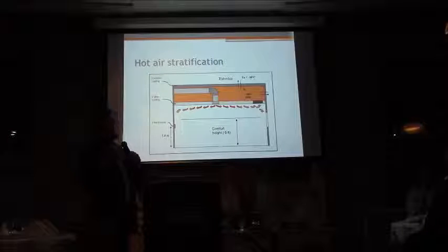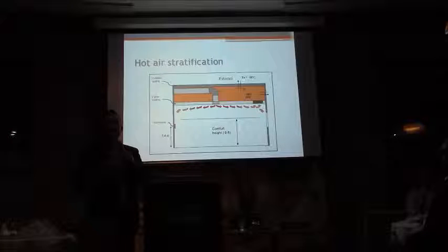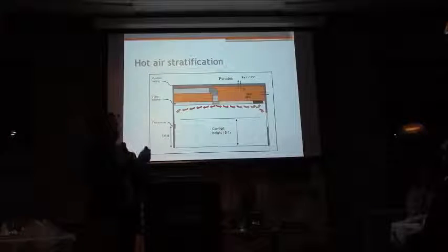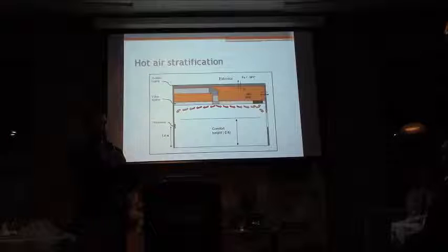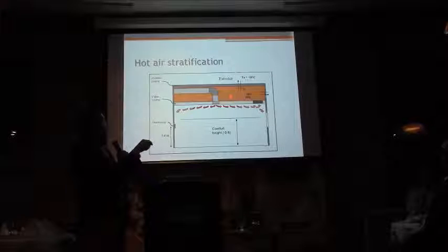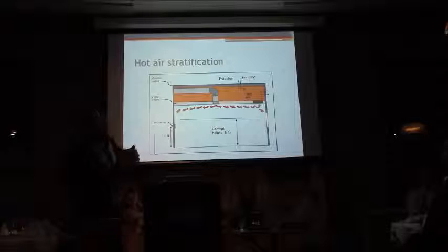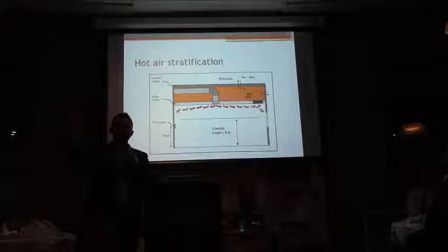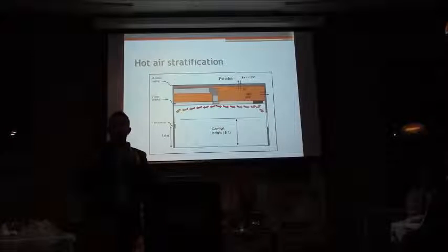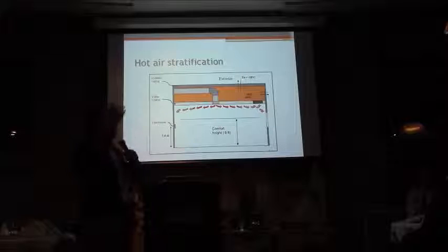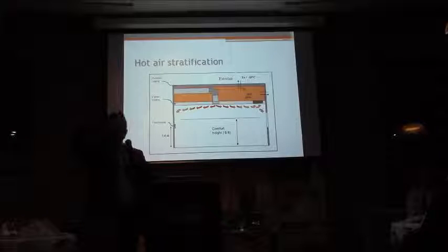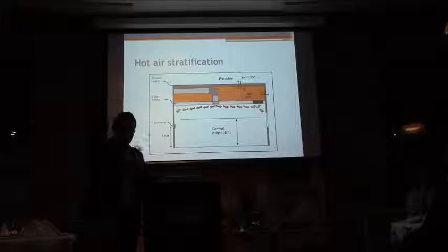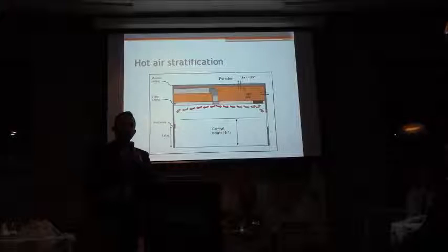basically the biggest loss that you get out of your ventilation is through hot air stratification. Whenever your hot air stratifies, you get a higher temperature inside your ceiling area, and because of that, you have higher losses through your building's envelope. So all that heat that's just stagnant up there, you want to find a way to throw it back into the occupied zone.